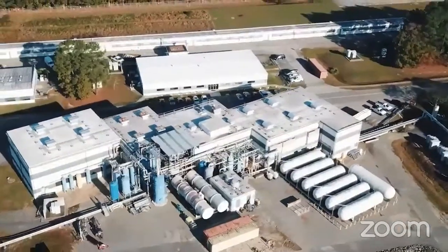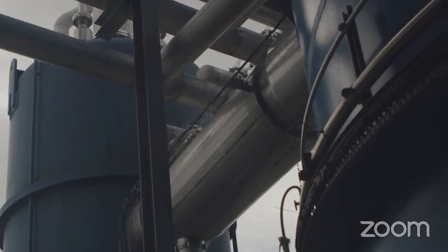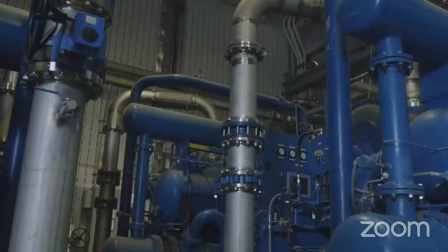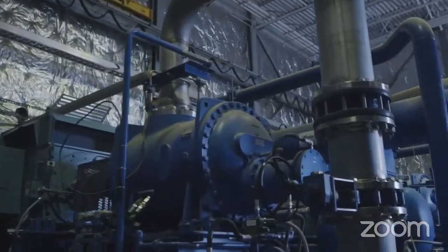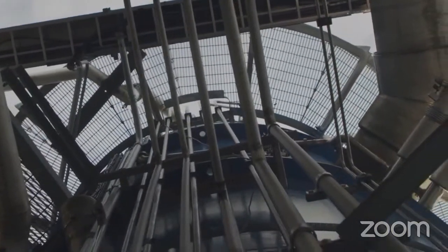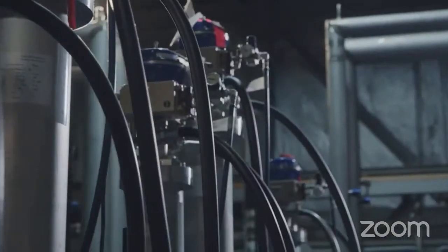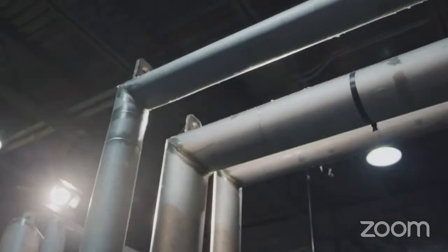Two of these are the largest single 2-Kelvin refrigerators in the world. Jefferson Lab's two central helium liquefiers together chill more than 30,000 gallons of liquid helium by compressing warm helium gas to high pressures and then sending it through cold boxes. The cold boxes usher the helium through a sophisticated system of tiny turbine expanders, each spinning thousands of times per second, followed by a set of complex heat exchangers.